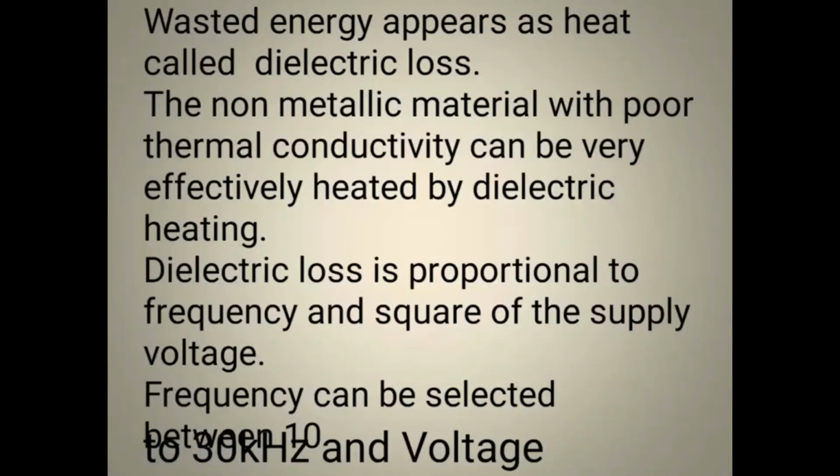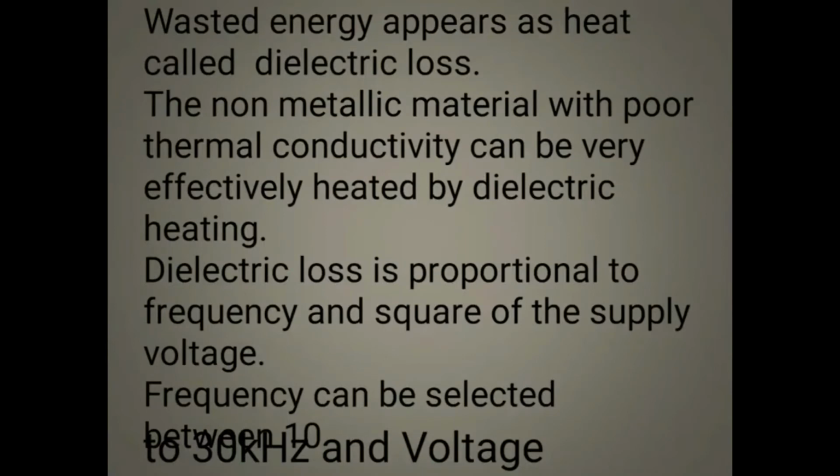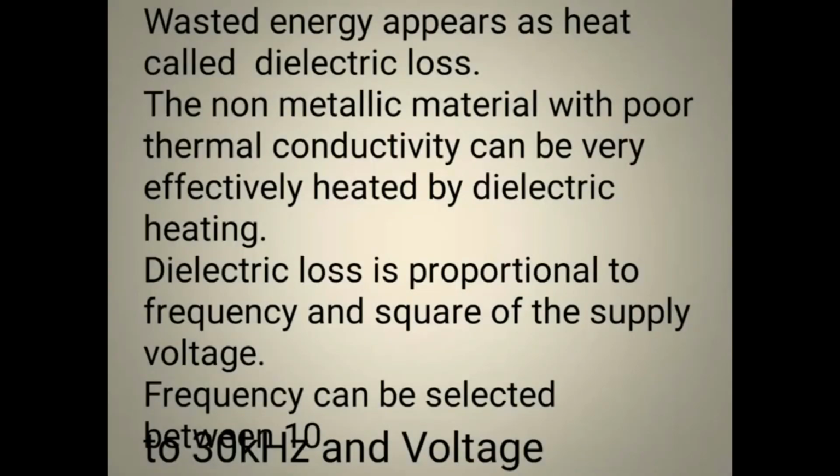Wasted energy appearing as heat is called dielectric loss. Non-metallic material with poor thermal conductivity can be very effectively heated by dielectric heating. Dielectric loss is proportional to frequency and the square of the supply voltage. Frequency can be selected between 10 to 30 kilohertz.